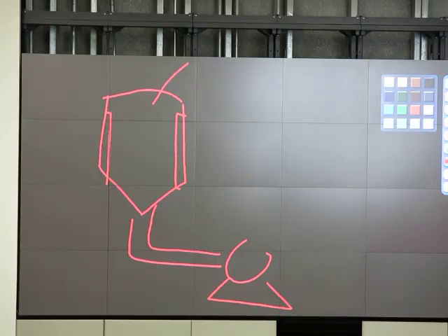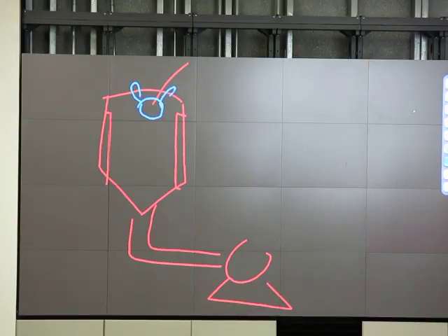What students put over there is a hard hat. A hard hat, hung with this cable, as an inlet diverter. So when the fluid comes, it doesn't flow directly to the outlet, and it has some time for gas to separate out. That is a poor boy inlet diverter. Once in a while, like one time every 2 years or something, this cable gets loose, and this hard hat goes down and blocks the hole.